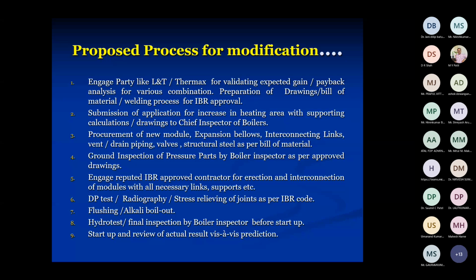We engaged so many parties who could use their expertise, and finally we prepared the drawing, bill of material and the welding procedure. It had to be approved by IBR also. We submitted an application with supporting documents to the Chief Inspector of Boiler. We had to take the permission because it is a registered boiler. This boiler was registered for this much heating surface and this much pressure. Now we are increasing the heating surface, hence we are changing the parameters of that registered boiler. So all the new parameters are to be communicated to the IBR authority. We have done all that procedure.